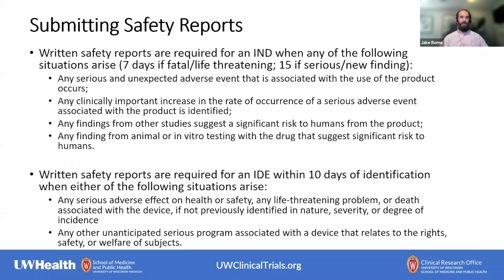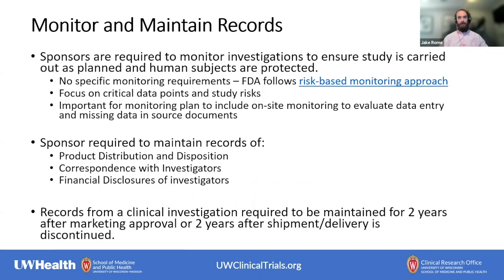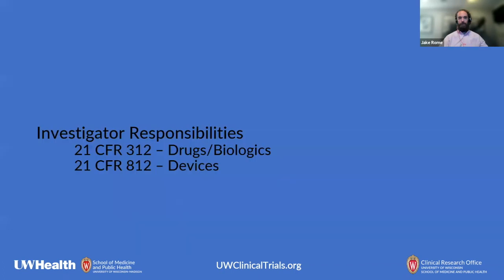There are also safety report requirements, again, mainly applicable to IND and IDE requirements. Although, as I mentioned, for non-significant risk devices, if there is some sort of serious adverse event that happens, that would need to be reported to the FDA, even if you've never submitted anything else to the FDA. And then as sponsors, you're also required to maintain records as mandated by the FDA, and also ensure monitoring of the study, which is important.